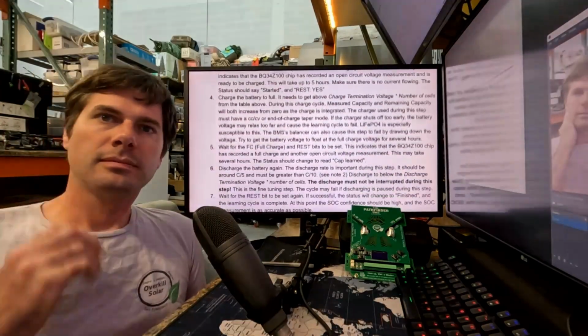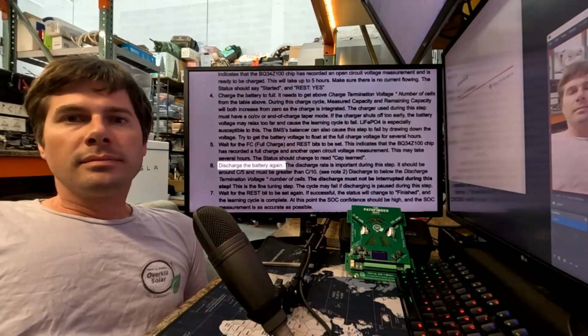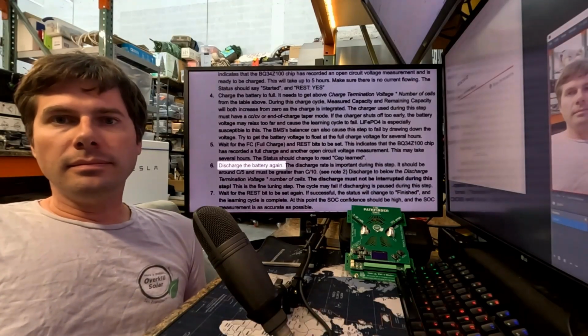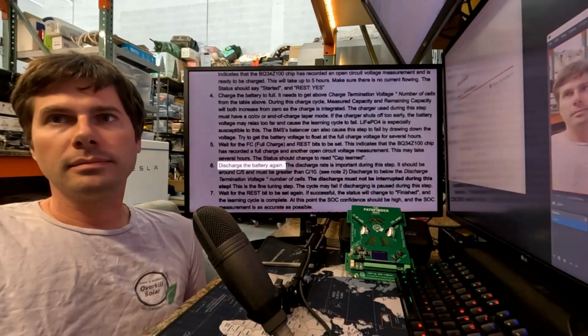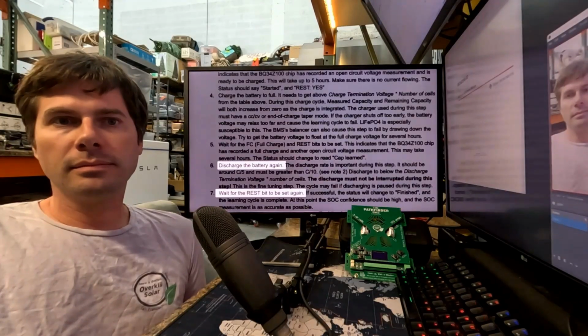And then afterwards again we do a full discharge to measure the capacity we get out of the battery, and wait again under 48 volts until the rest bit sets. So it's basically charging, discharging, and it measures the capacity in both ways and sets the parameters accordingly. A fairly easy step actually.